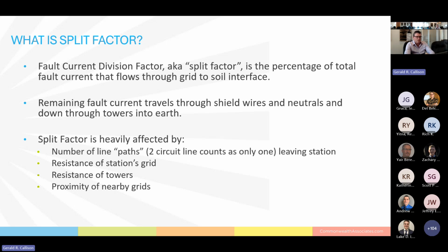Well, that current is leaving through shield wires and neutrals for lines that enter the station and are connected to the ground grid when they enter the station. It leads through those shield wires and neutrals and then down those towers and into the earth and back to the source. Split factor is going to be heavily affected by a couple of things. It's going to be affected by the number of line paths.